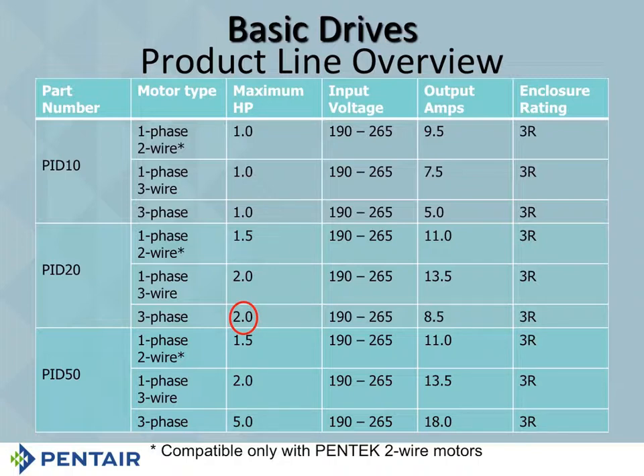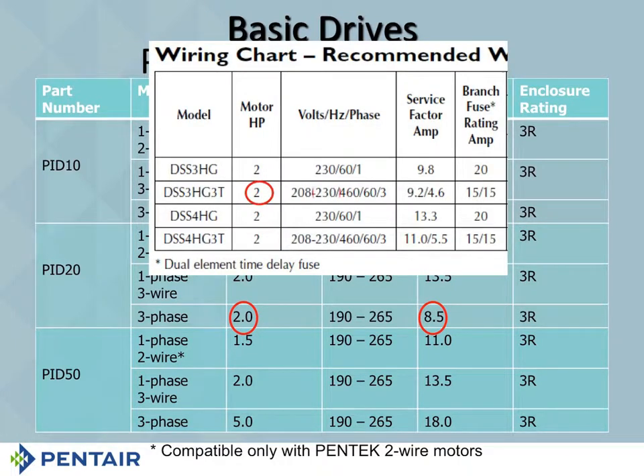This is really, really important because this is the DSS4 HG3T. And you're going to notice that whether you're using the DSS3 or the DSS4, it is a 2 horsepower pump. It is 230 volts, and you'll notice that the 3-phase service factor amps at 230 volts, even for the DSS3, is 9.2. If you look at the DSS4, it's 11. So remember, it says here 2 horsepower, and that's a 2 horsepower pump. At least that's what we're calling it. And of course, it's only got 8.5 max load amps, and you're at 9.2. Probably isn't going to work. Okay, it definitely isn't going to work.